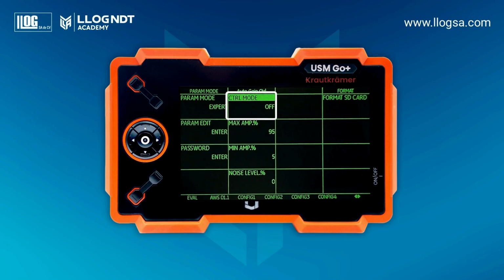The automatic gain control adjusts the echo amplitude to keep it within a specified range, compensating for amplitude variations. A maximum amplitude and a minimum amplitude are defined for the echo inside the gate. It is also possible to set a noise threshold. The last function allows formatting the instrument's SD card.